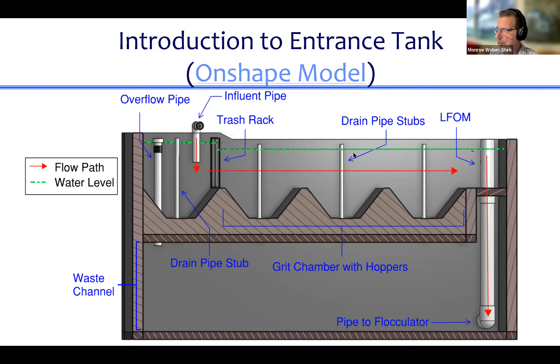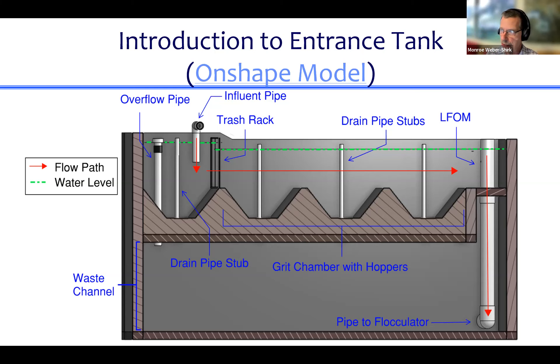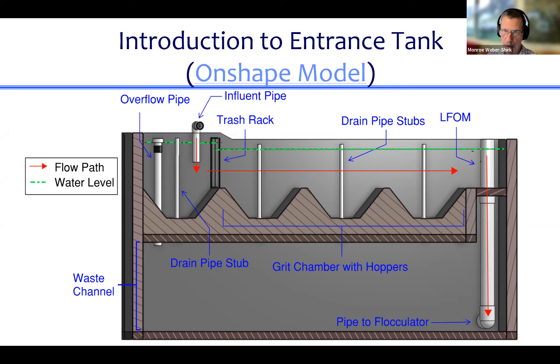There are four white pipes plugged into PVC couplings embedded in the concrete at the bottom of the tank. When the operator wants to drain the sludge of sand and grit out of one of those hoppers, they just grab one of those white pipes, pull it up, and it pops out of the socket at the bottom of the tank. The sludge then drains into a channel right below the tank, connected to the plant's drain system.